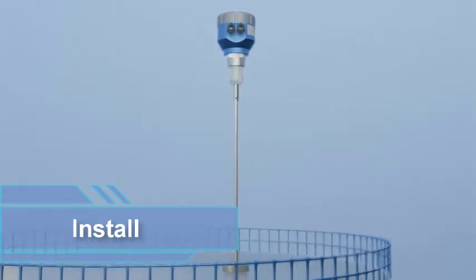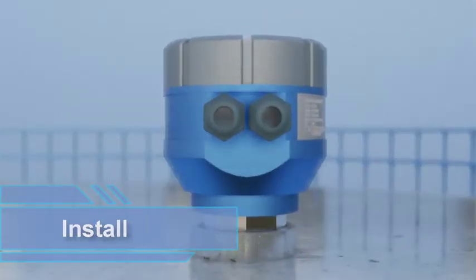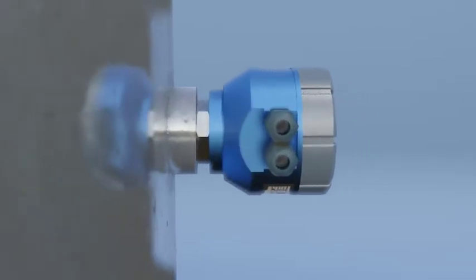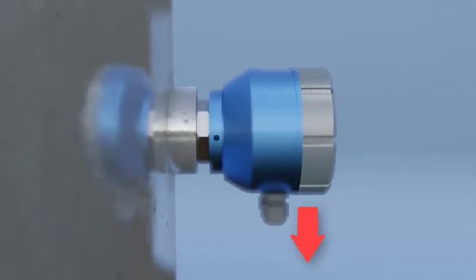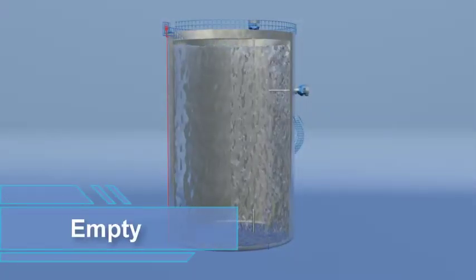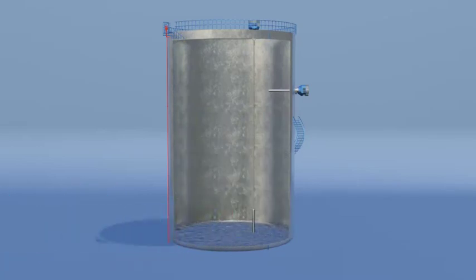First, install the device as shown in the instructions manual. For the SM630, if installed horizontally, make sure that the glands are directed downwards to avoid water or moisture. Ensure the tank is empty before installing; if not, empty it.